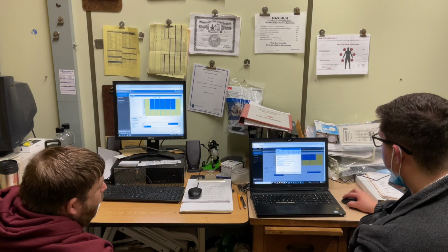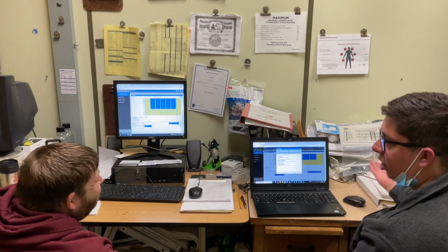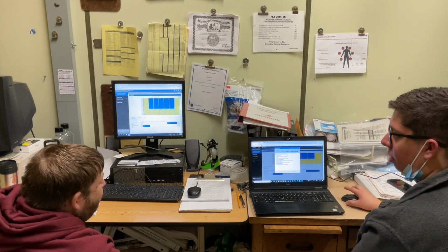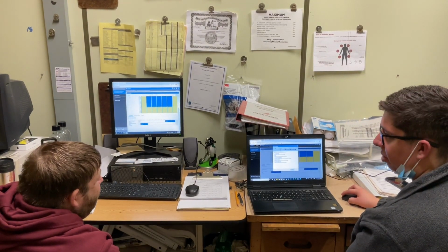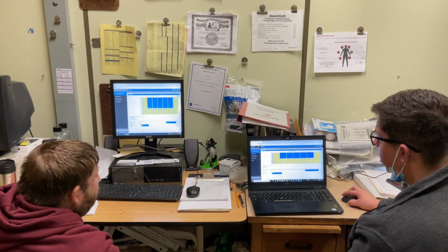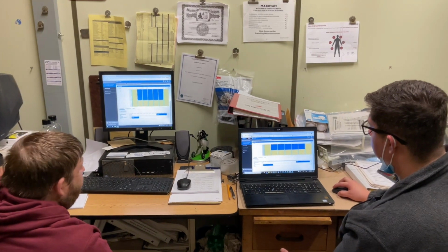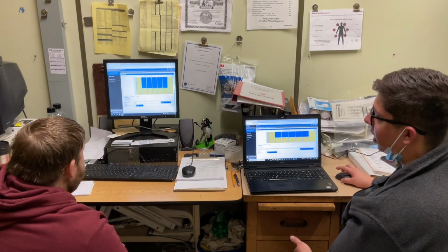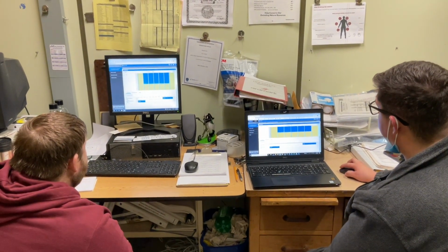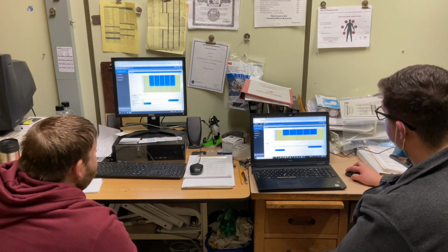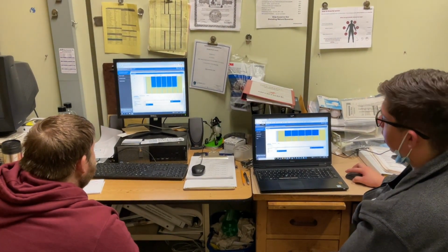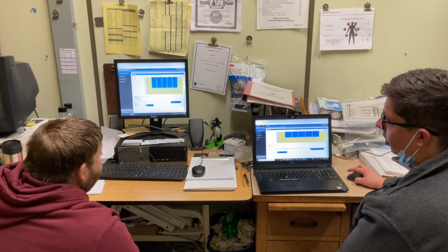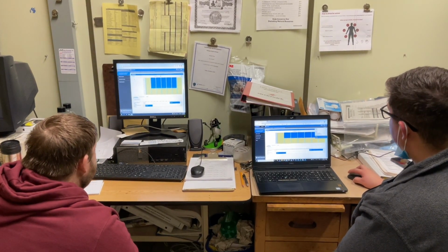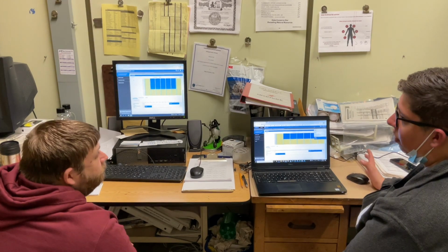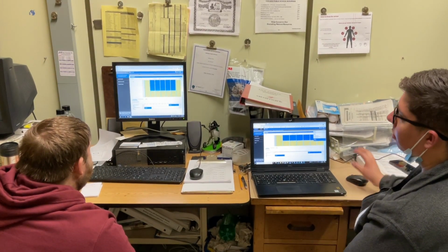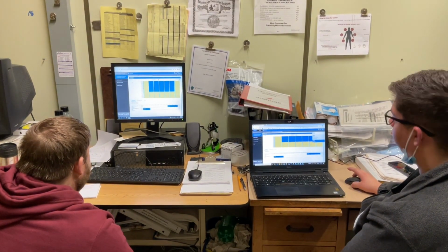Yeah, I think we did long running. We knew it was going to be cold for like 2 days, so we went long running, ran it for 2 days, and kept it occupied. After that, they will stay in this tree here, and you could see the date. It's not going to hit that date again, it'll just stay on there. So you can always delete these with the little trash can there, unless you edit and change the date range. That's on page 3. Like I said, you can get to that on any unit ventilator, and that'll change all of them, because there's one master schedule just for the unit ventilators.